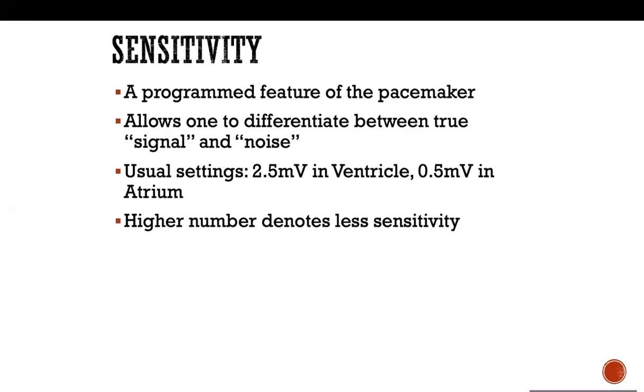So what's the problem if you make the device very, very sensitive? Let us say you made it 0.5, for example. You're going to see anything that is above 0.5, so sometimes external noise might give you some electrical signal. You see it on the ECG. A little bit of noise might give you some signals on the ECG, and those are artifacts. The same thing can happen with a pacemaker. You don't want it to be very, very sensitive because it might pick up artifact. And if it picks up artifact, it's going to think this is a QRS. And if it sees a QRS, then it's not going to pace. So this is kind of the trick. You need to make it sensitive enough to see every QRS, but not too sensitive, so you will try to avoid artifact.